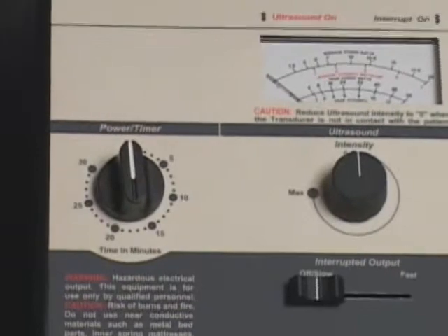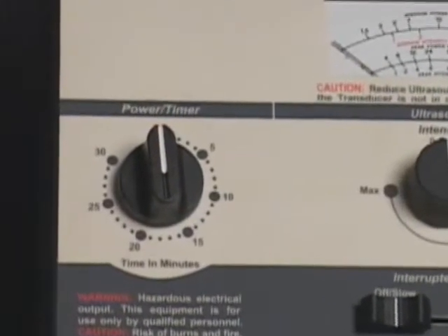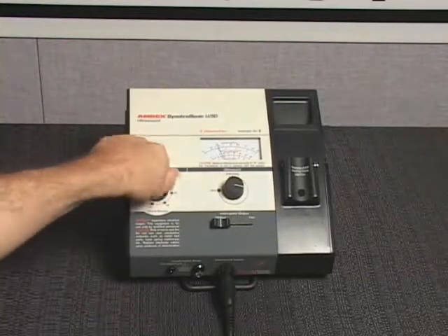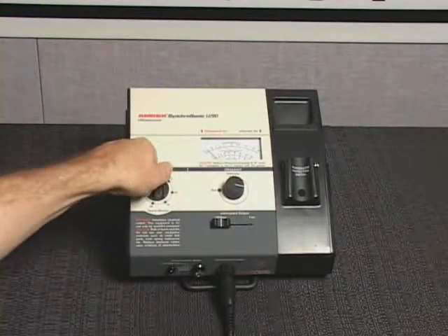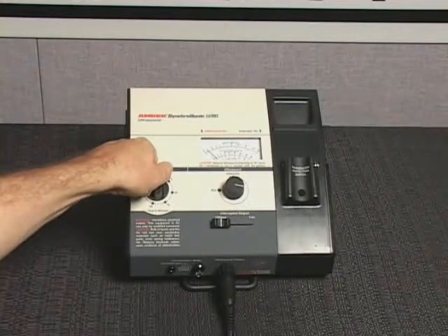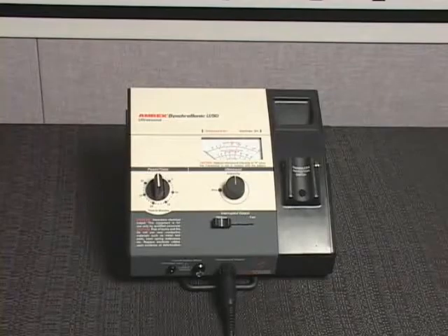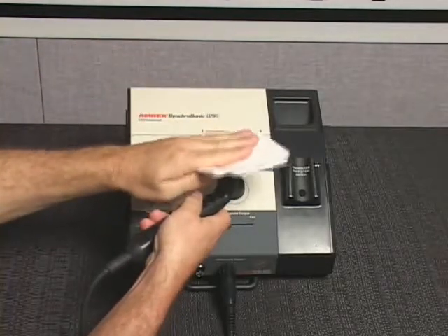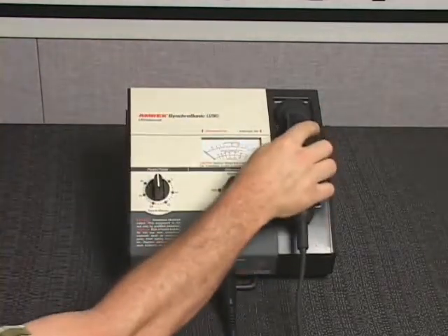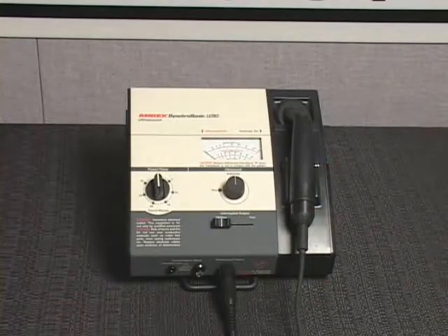The AC power will shut off and a bell will sound when treatment is completed. To initiate early shutoff, rotate the power timer knob counterclockwise to the off position. The AC power will shut off and a bell will sound.